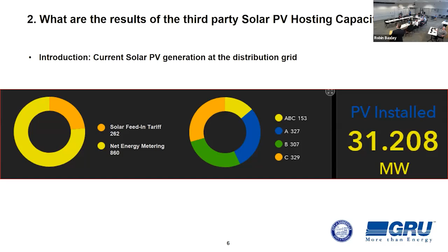On the right-hand side, I'll talk about how distributed solar PV can impact a distribution system. It can affect our main feeders and laterals, the primary wires and cables. It can impact our loads and voltage regulation, as well as our protective devices and SCADA energy management system. It can also affect fault current, slightly increasing the available fault current on these circuits, and it can impact power flow by creating reverse power flow conditions in some scenarios.